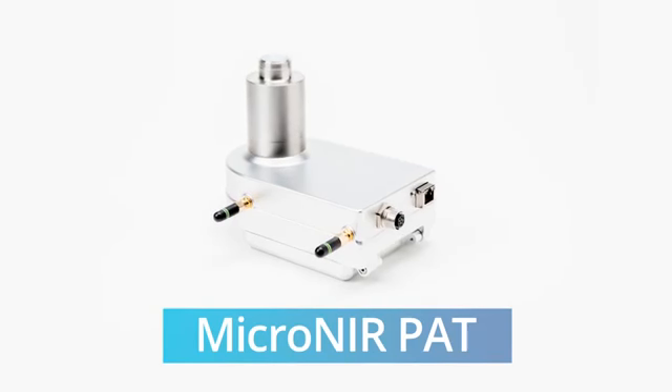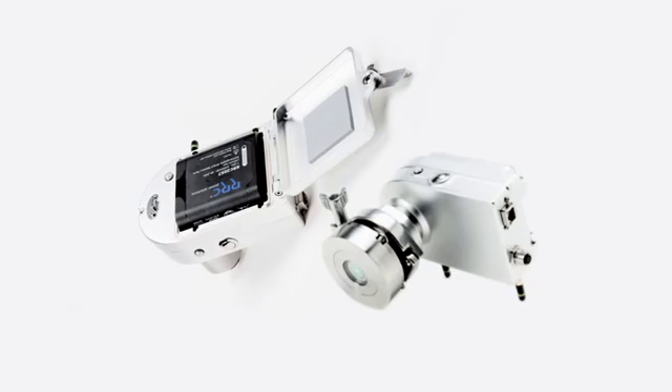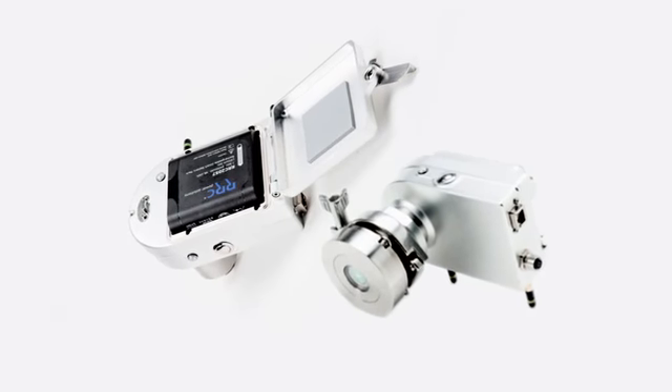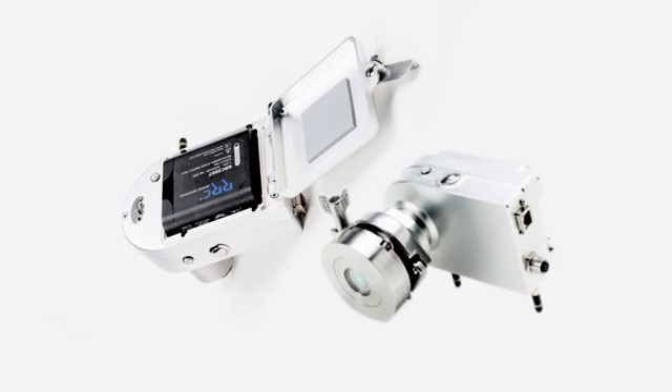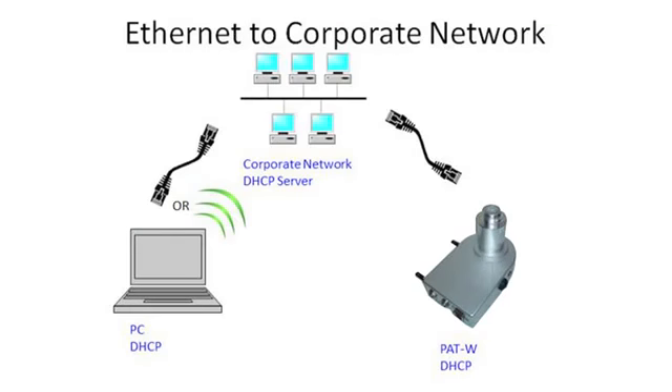The MicroNIR PAT is designed for in-line process monitoring. It can be battery powered for up to 8 hours of continuous operation or run off an external power source. Data can be transmitted wirelessly to the process controller via Wi-Fi or connected by an Ethernet cable.